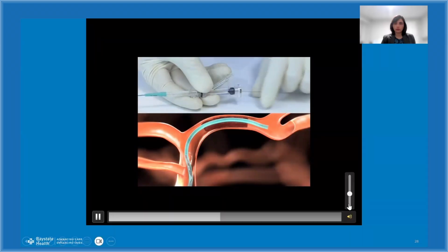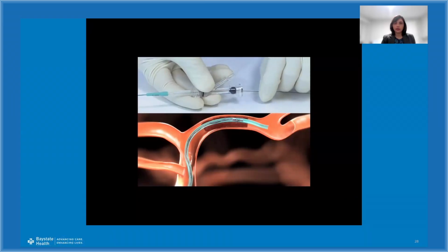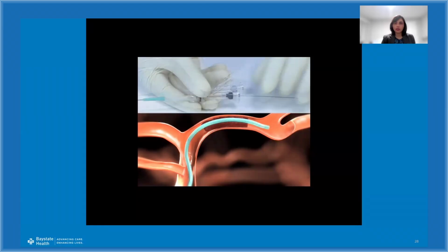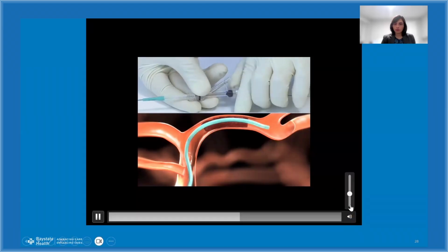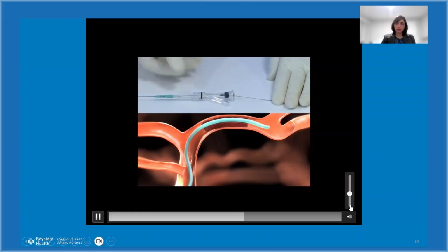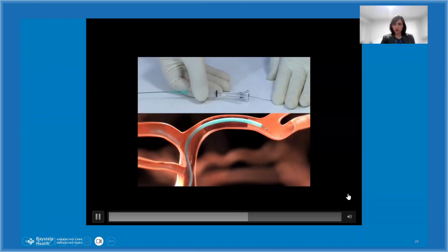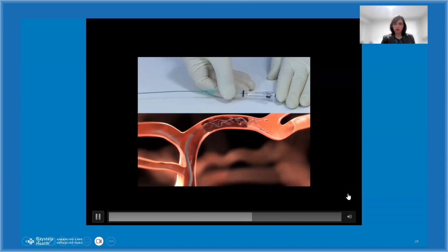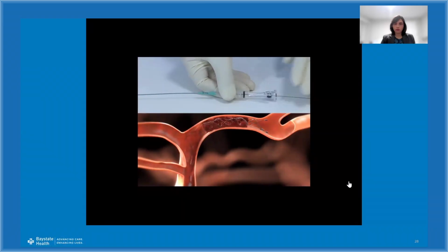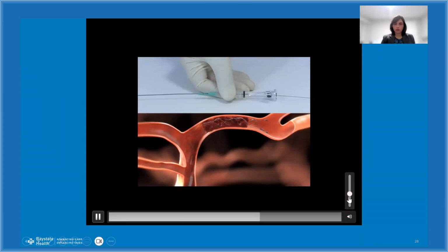With the aid of fluoroscopic imaging, carefully advance the Solitaire FR device until the end of the microcatheter, to engage the clot. To deploy the Solitaire FR, loosen the RHV. Then carefully withdraw the microcatheter while holding the Solitaire FR in place until the microcatheter tip covers only the proximal marker of the device. The usable length of the deployed Solitaire FR should extend.